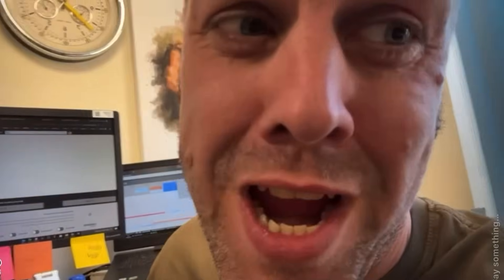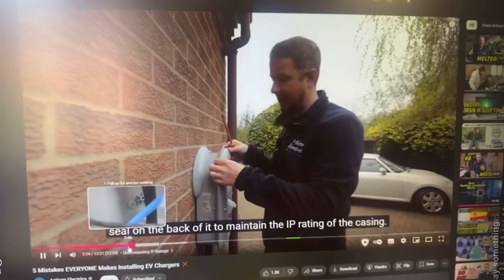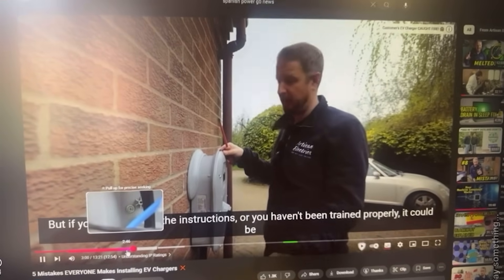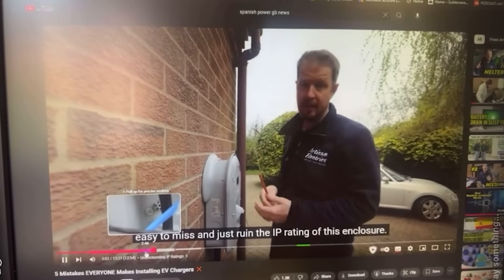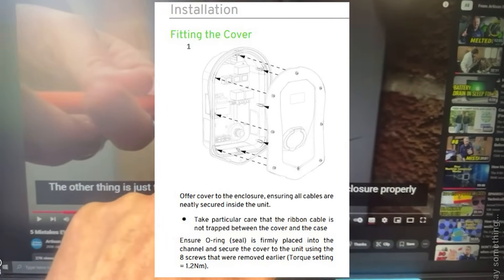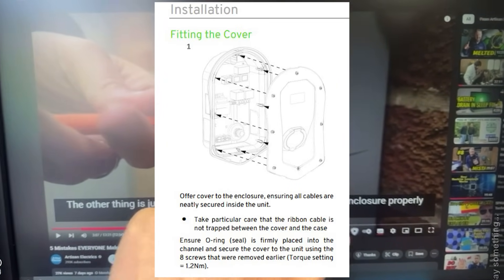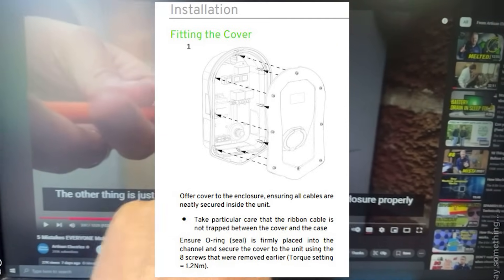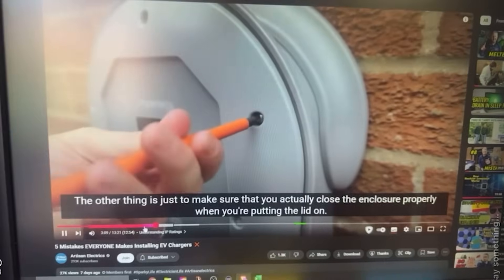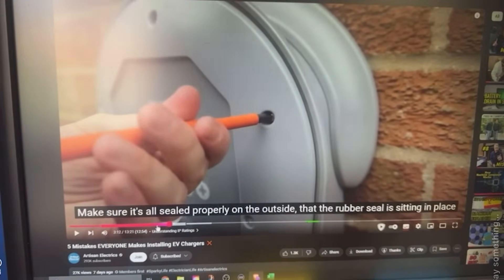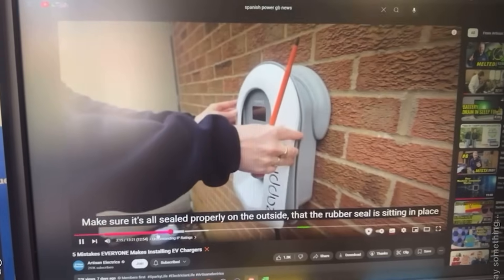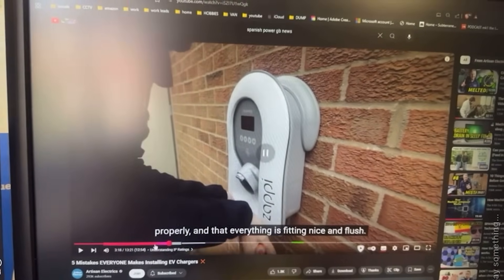Playing Jordan's video: 'To maintain the IP rating of the casing — all detailed in the manufacturer's instructions — if you haven't read the instructions or been trained properly it could be easy to miss and ruin the IP rating of the enclosure. It's clearly stated in the Zappi instructions that the screws should be calibrated with a torque screwdriver because over or under tightening affects the IP rating.